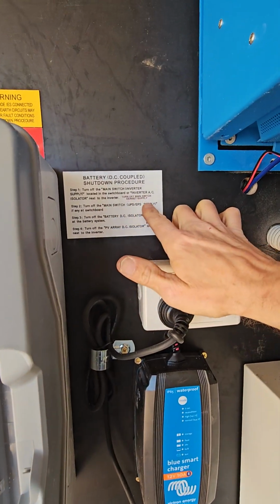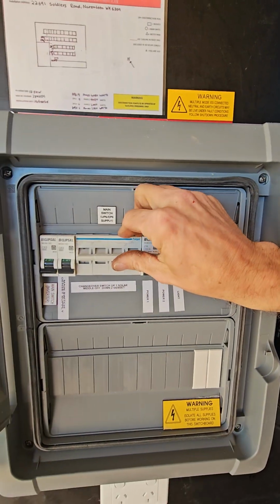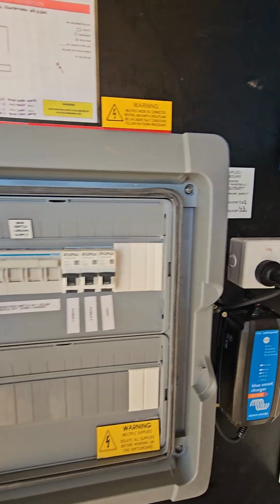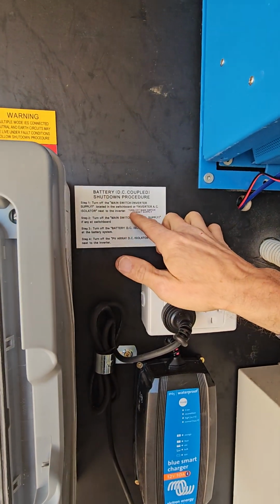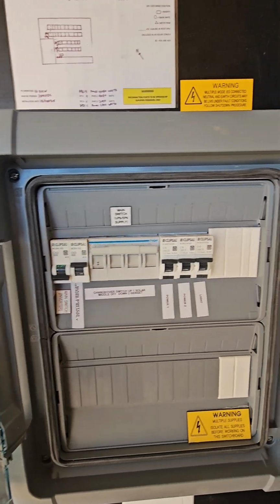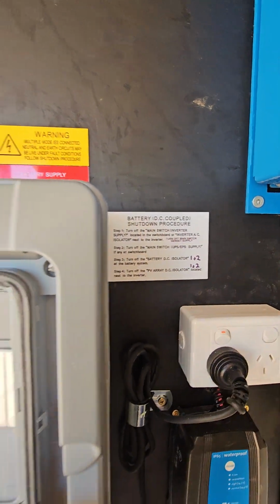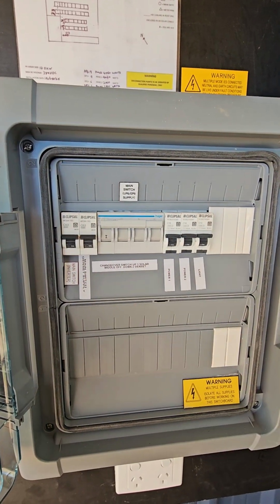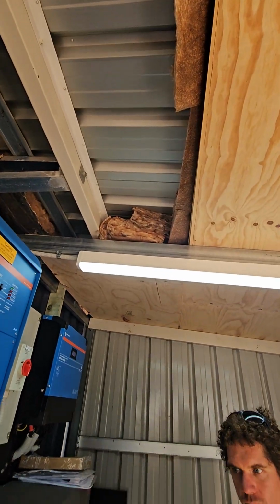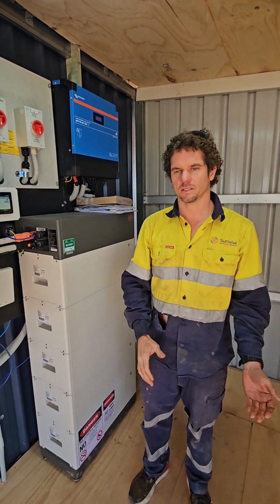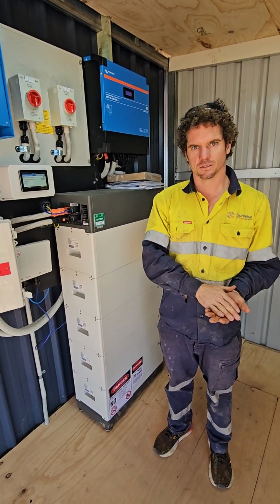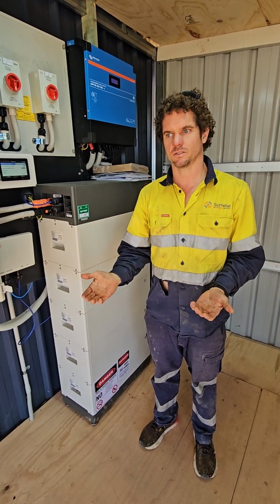The main switch UPS/EPS supply is your big changeover switch. Put that back up to the number 1 position, the normal position. Turn back on the main switch generator supply, which is this second circuit breaker here. Then turn back on the main switch inverter supply, which is that one there. That's a safe de-energization and safe energization of the system.